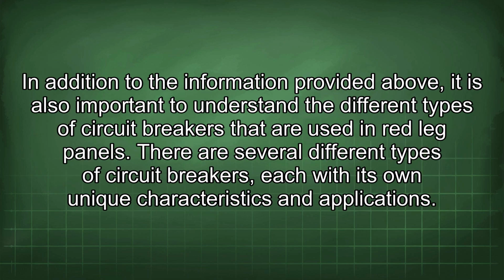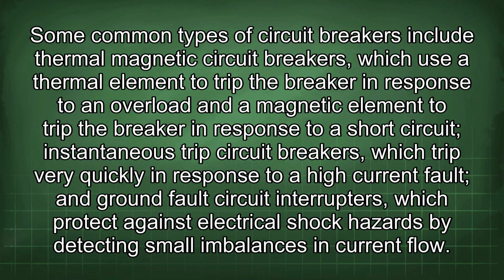In addition to the information provided above, it is also important to understand the different types of circuit breakers that are used in red leg panels. There are several different types of circuit breakers, each with its own unique characteristics and applications. Some common types include thermal-magnetic circuit breakers, which use a thermal element to trip the breaker in response to an overload, and a magnetic element to trip the breaker in response to a short circuit. Instantaneous trip circuit breakers, which trip very quickly in response to a high current fault, and ground fault circuit interrupters, which protect against electrical shock hazards by detecting small imbalances in current flow.